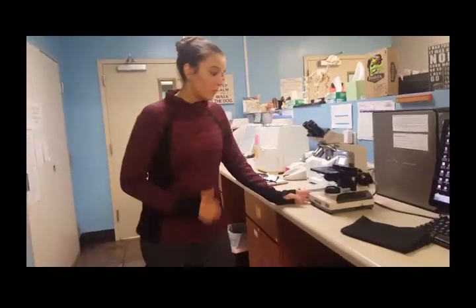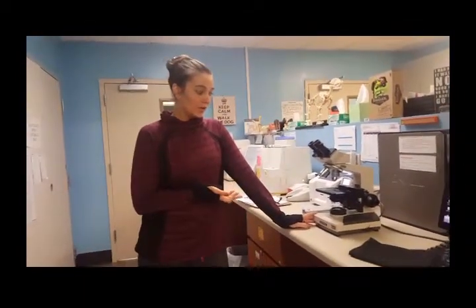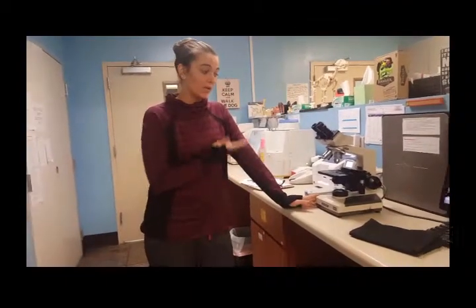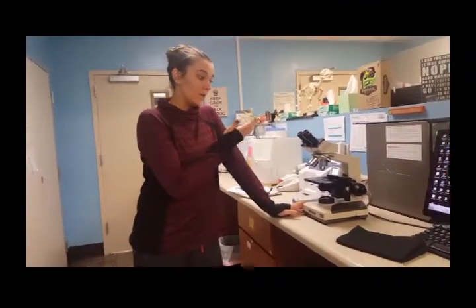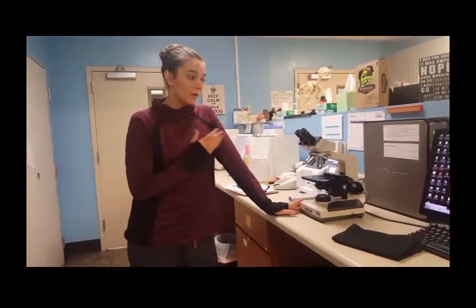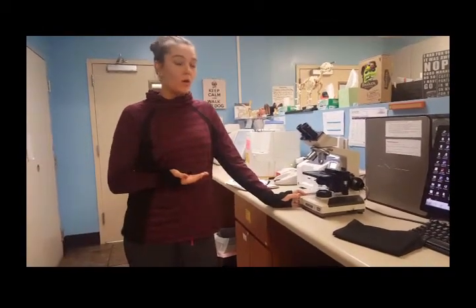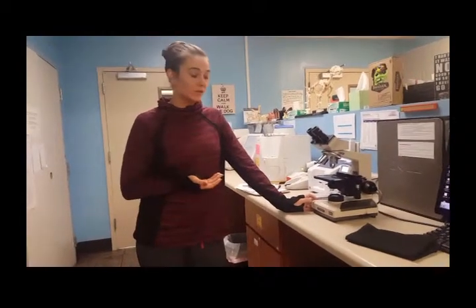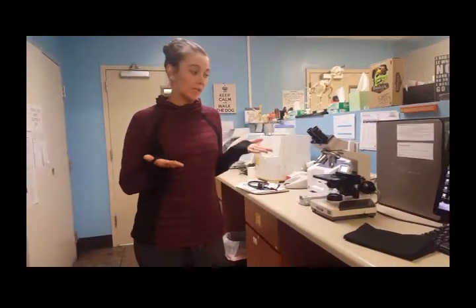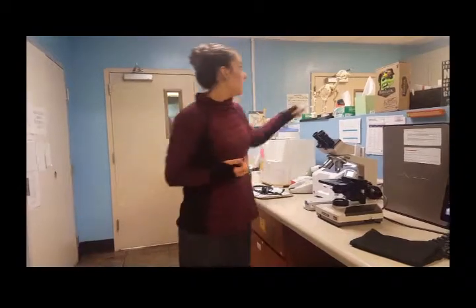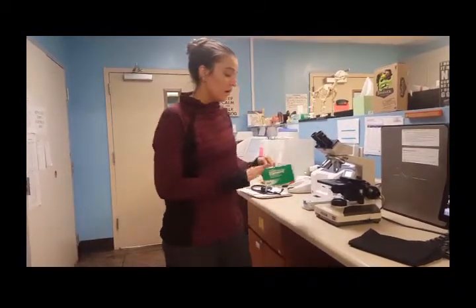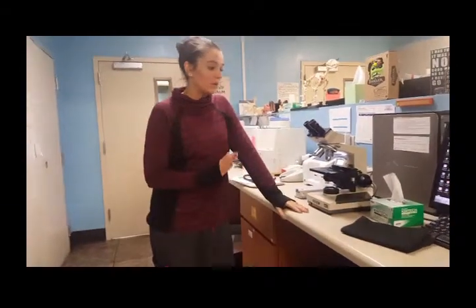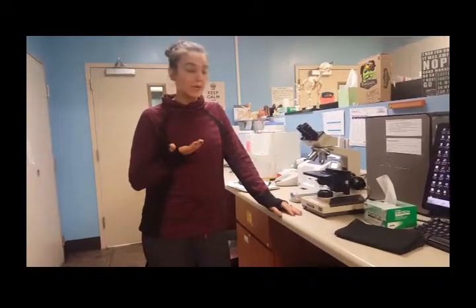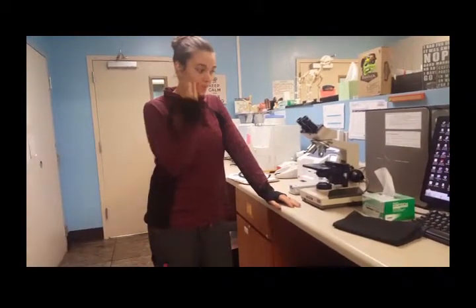There's a couple different things that you need to remember with the microscopes. When you're getting, let's say, a brand new microscope, you're going to have to calibrate the lenses to what type of testing you're going to be doing. The stage micrometer, you can buy one, but if you only have 1 to 2 microscopes and you're not going to be having a bunch of different microscopes, it's usually better to borrow one from a university or any other type of laboratory diagnostics area. And then you always want to have just some Kimtech wipes available. That way when you're done using, say, an oil immersion slide, you can always clean your lens after use. Always wipe off the lenses after you're done using them.